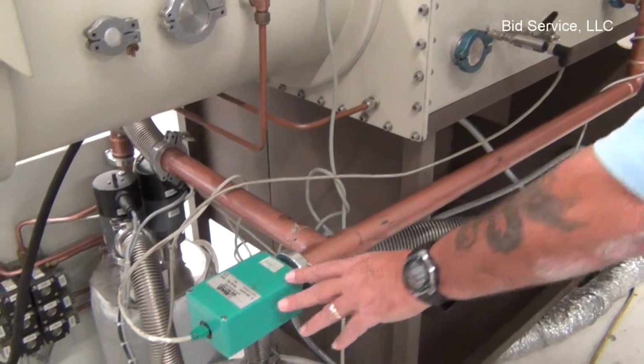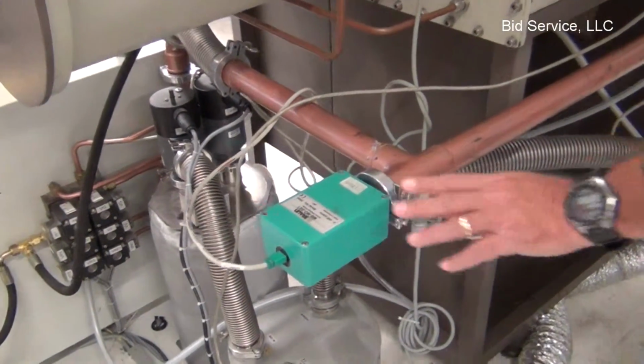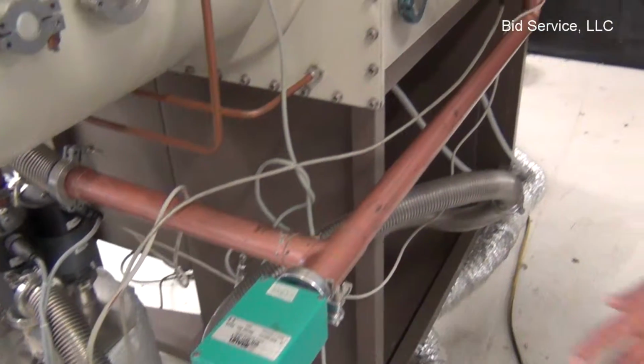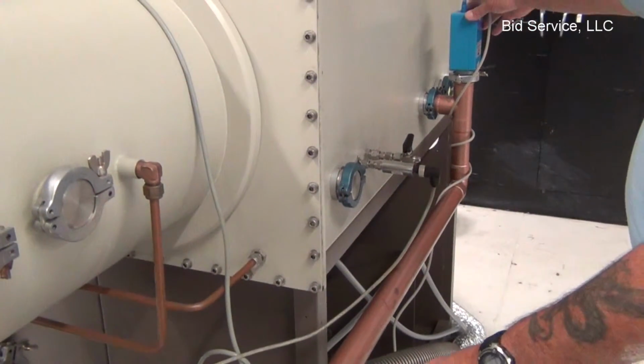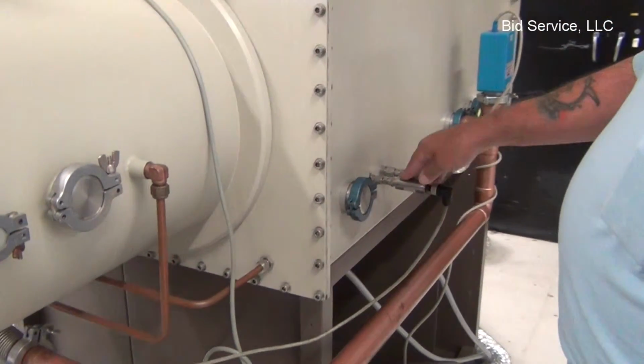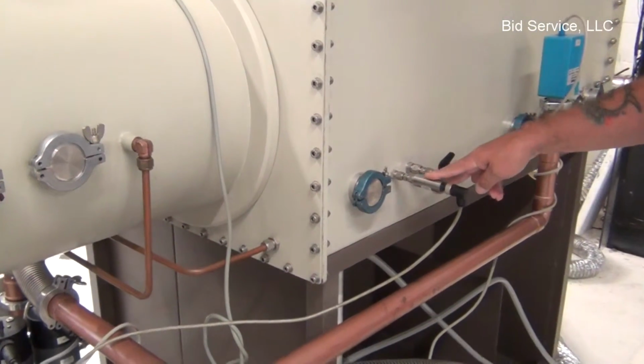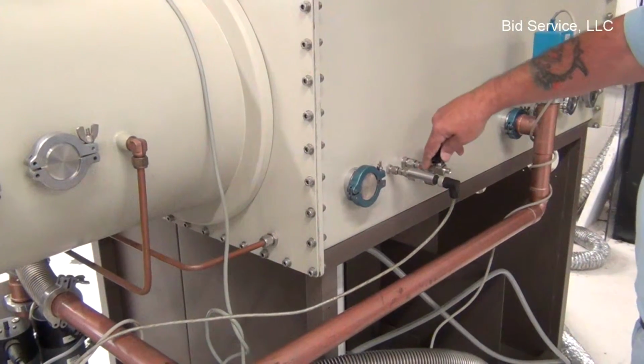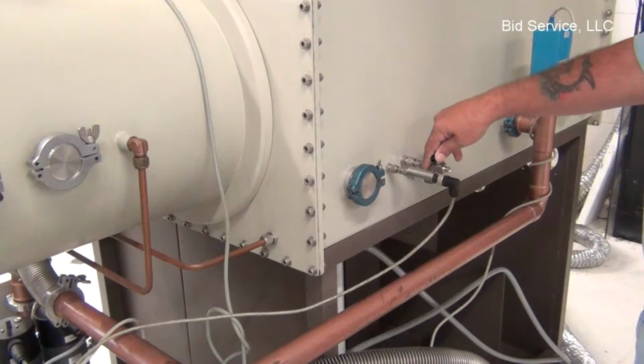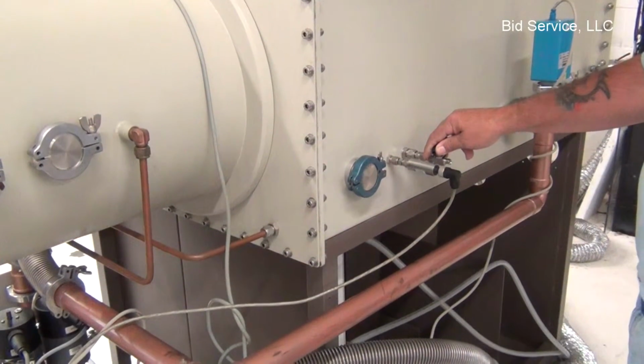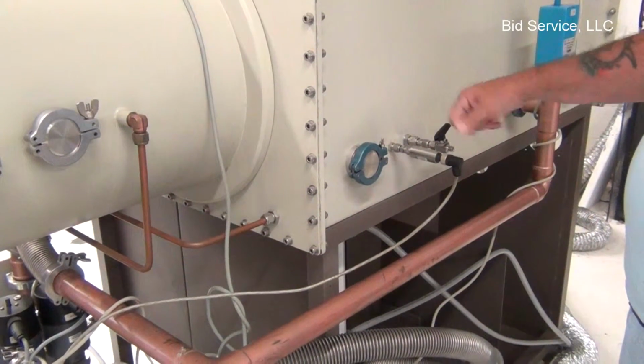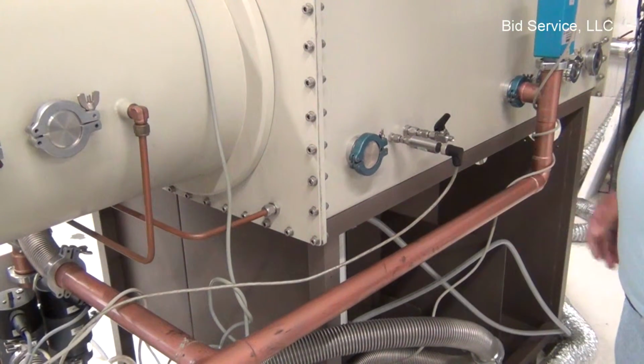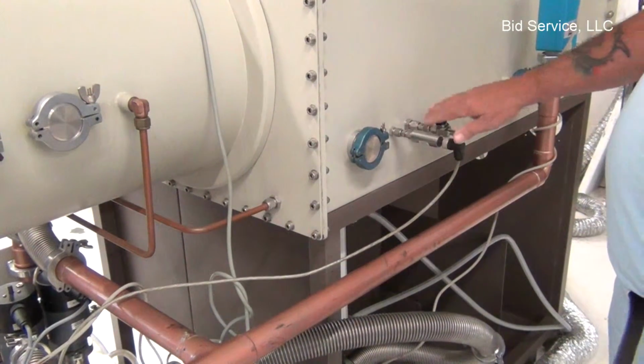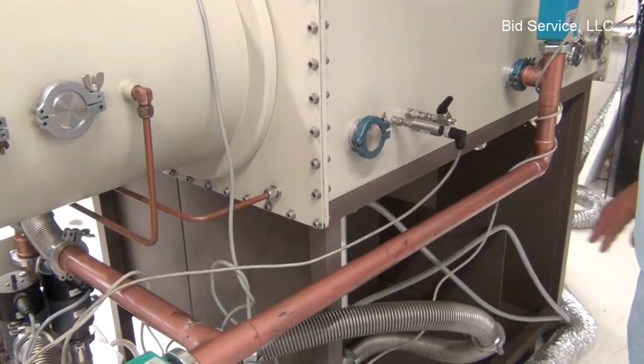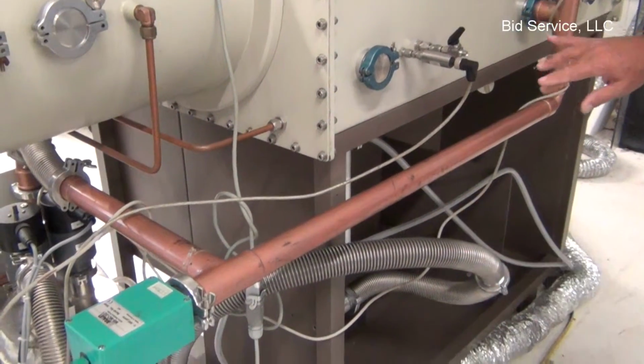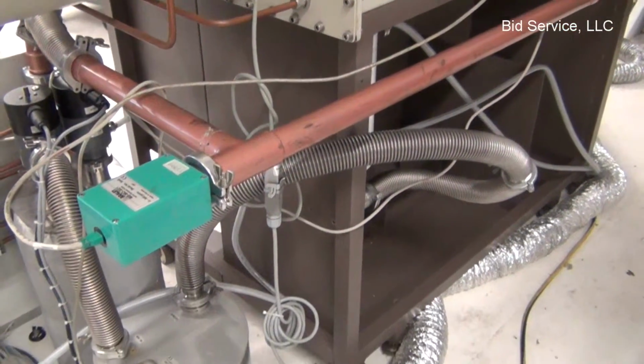Okay. We have here our oxygen and moisture sensors. They're in line with the box. This is the pressure sensor for the box. And this valve is here to be able to purge the box with nitrogen when you first set it up. You can open it up and it'll bleed nitrogen out. All this stuff will be disconnected and packed. I wanted you to see where it goes so when you put it back together.